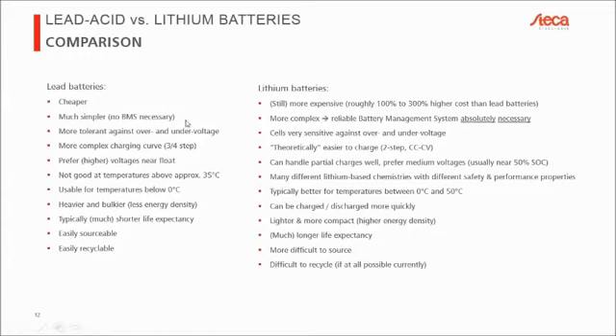Lead batteries are much simpler. We typically don't have any electronics in lead batteries. For lithium batteries, the situation is different. We have what's called a BMS, or a battery management system, which should always be installed directly in a lithium battery. It could be external as well, but my strong recommendation is to only use lithium batteries which have an integrated BMS. Lead batteries are a little bit more tolerant against over or under voltage.